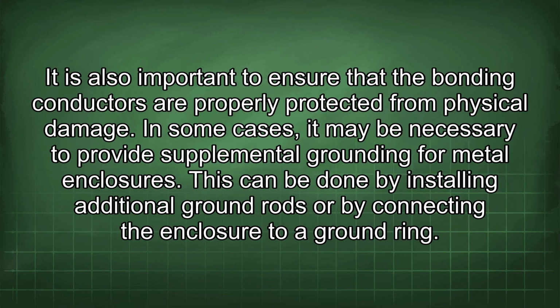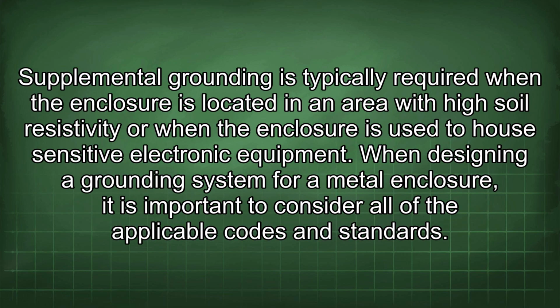It is also important to ensure that the bonding conductors are properly protected from physical damage. In some cases, it may be necessary to provide supplemental grounding for metal enclosures. This can be done by installing additional ground rods or by connecting the enclosure to a ground ring. Supplemental grounding is typically required when the enclosure is located in an area with high soil resistivity or when the enclosure is used to house sensitive electronic equipment.